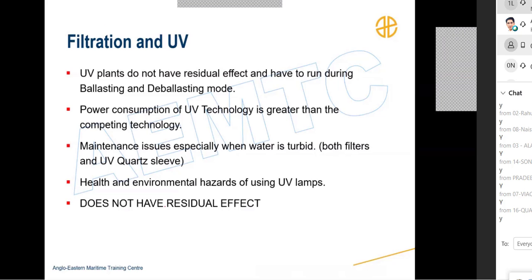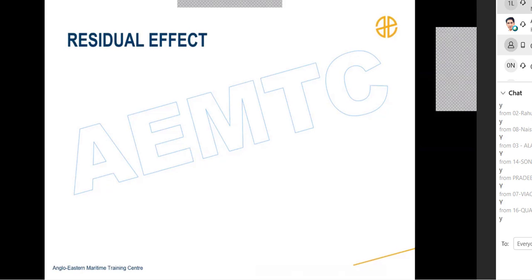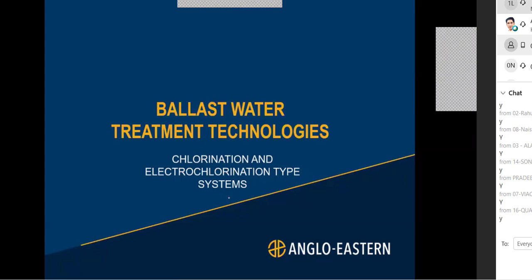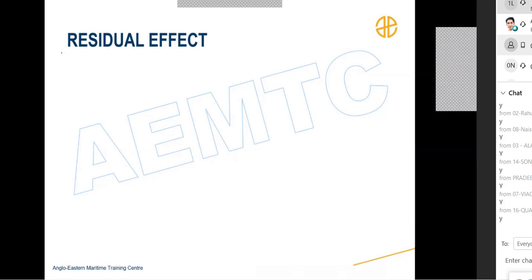Okay. What we need to understand in the system is your residual effect. That is not there in this system, which is there in your chlorination. So now let's move on to chlorination. Before we discuss chlorination, we need to understand what exactly is residual effect. So you remember in your STP, we are doing residual chlorine test. Why are we doing so? Because some amount of chlorine remains. It is not used up, and this can go into water.